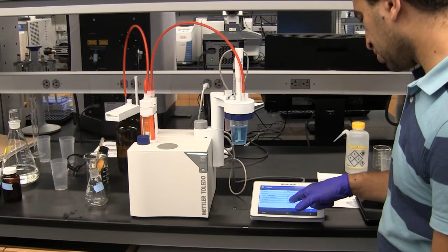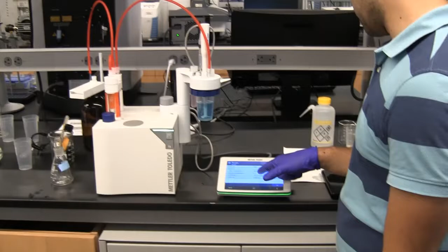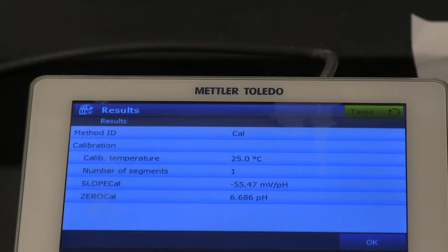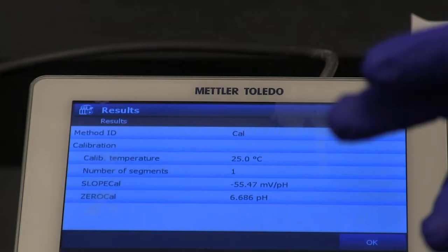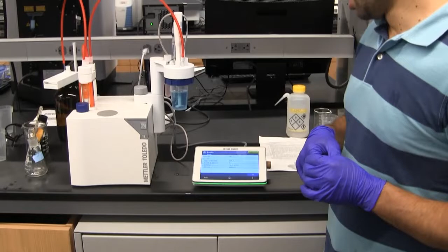In the end, you look at the value of zero cal, it has to be between 6.7 and 7.2, which is quite close. And also the slope cal has to be between minus 55 and minus 59. So that should be fine. That means your system is calibrated. If not, you probably need to check each pH buffer on its own. And if one of them is not okay, you have to throw the one you used away and use a new batch and keep the rest as they are. So now we will see how to check each of them.